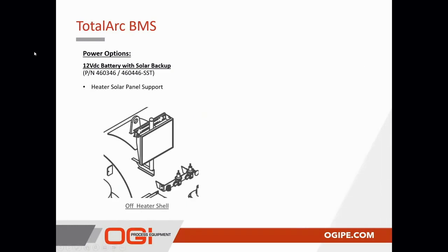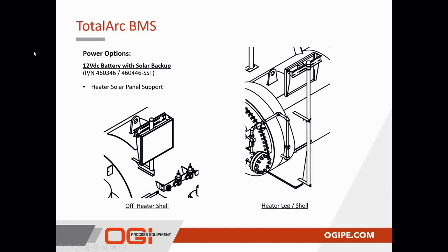When solar panels are required for the BMS system, OGI will ensure that the heaters are equipped with supports and braces to allow the solar panel to be mounted and positioned as necessary. I've shown two different versions here. One is for a larger heater, where the solar panel is supported off the heater shell. And the one on the right is supported off the heater leg with another support off the shell just to add stability. The one on the right is something we would typically see for a smaller heater. And of course, the one on the left you might see for a larger heater or multiple panels on a larger heater.